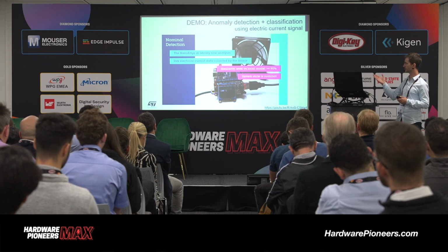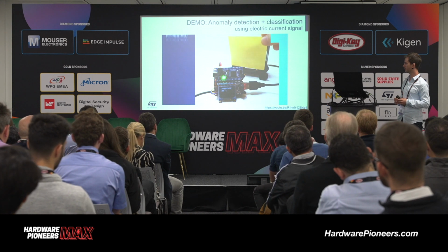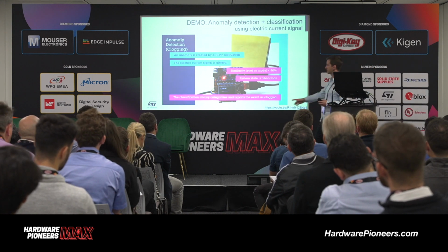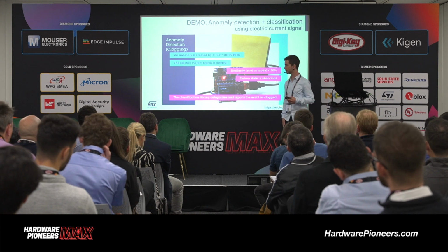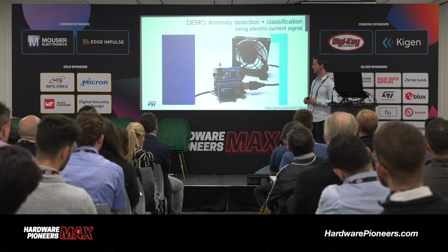So here we learned the normal behavior of the motor, of the fan, and when we clog it, not only does it say error, but also clogged. So we did anomaly detection and classification.